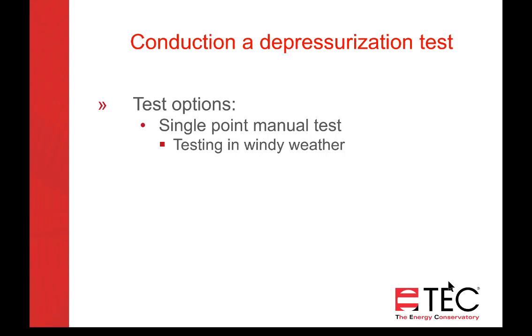And what I recommend is if you leave that go for 30 seconds, then do a long-term average once you get it up to 50 for 30 seconds also. And that's a nice thing about the 1000, it has a little counter on there that'll tell you how long it's been on long-term average, and you can match your baseline with a CFM at 50 time averaging.